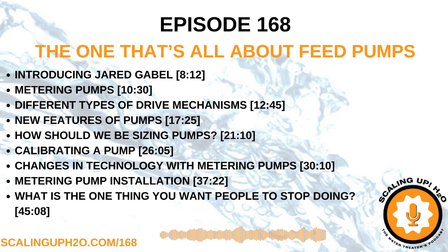Yeah, I think when you look at those types of pumps that say that, then of course you want to make sure accuracy is a very key thing, because your end users and your customers that are using these are really paying for the chemical. And over time the operating expenses and the capital expenses of the pumps just pay for themselves with the chemistry. So it's really important to get a pump that's very accurate. You know, you're looking at plus or minus 1%, plus or minus 2% is generally where you're going to be, depending on the application. One of the things that we look at, though, is that steady state accuracy.